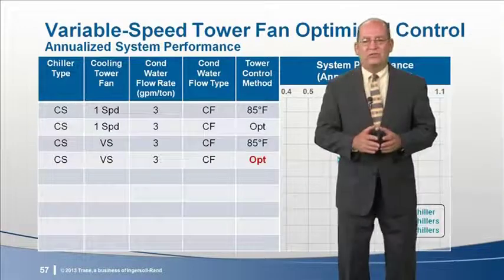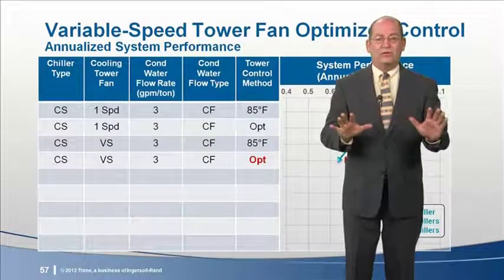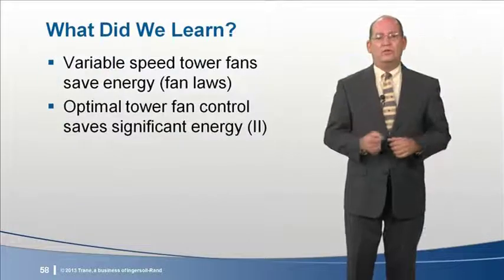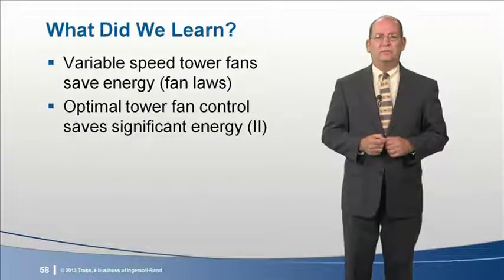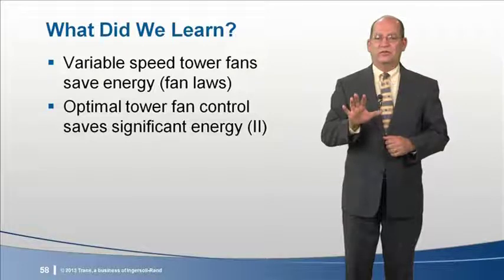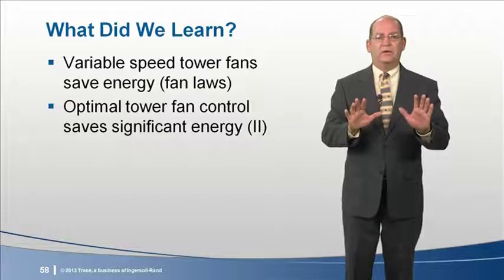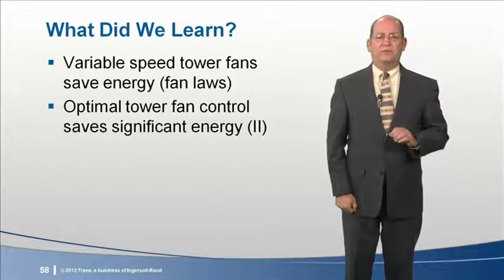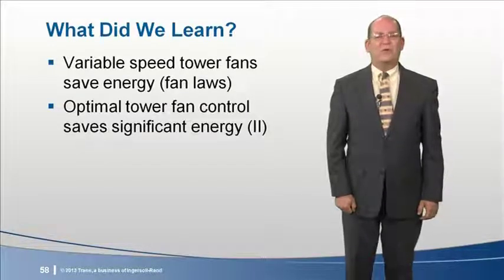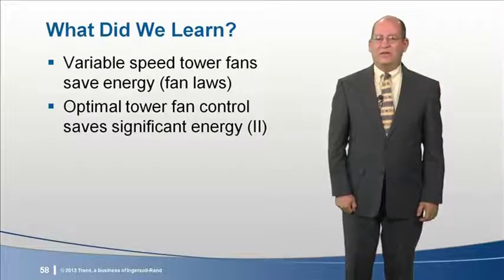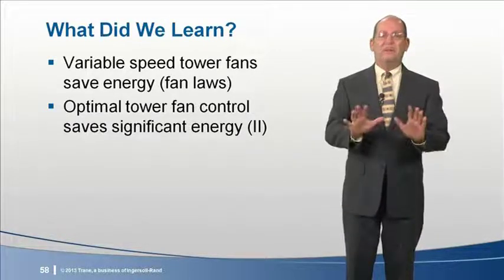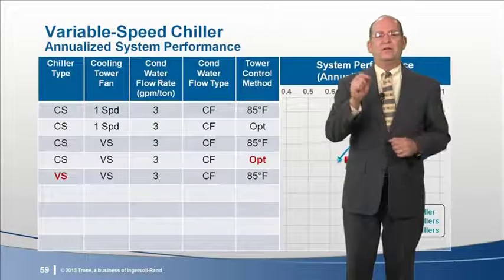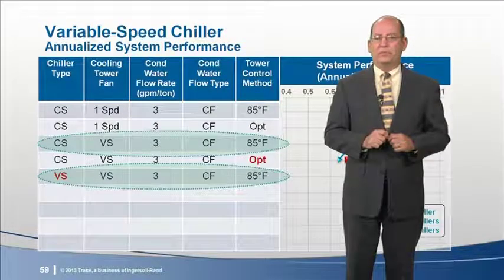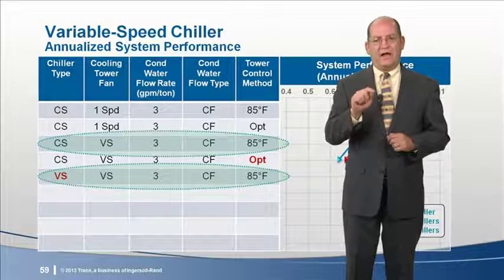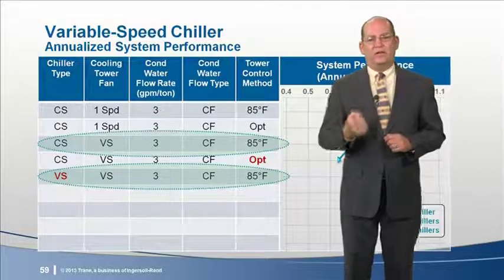Now, some people might stop here, but there's still some low-hanging fruit to be picked. For these 2 alternatives, here are our conclusions. It's no surprise that since cooling tower fans are free discharge fans, their savings are nearly cubic and that they're a great efficiency measure. And we again see that optimal tower fan control is a significant energy saver. But let's make the system performance better yet. Today, many people select chillers with variable speed drives. So let's look at that option and compare it with a constant speed chiller.